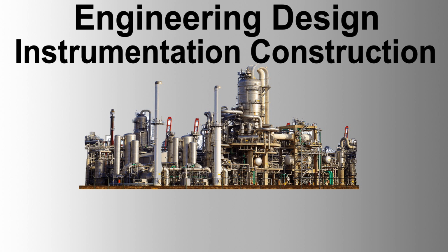Insulation shall be provided for impulse lines wherever required. The insulation should normally consist of mineral wool, wrapped around and covered with a weatherproof material. The chloride content in the mineral wool insulation shall not exceed 10 milligrams per kilogram. Technical requirements. Flow instruments. Differential pressure instruments for flow measurement should be located within a distance of 1 meter from the measuring element. Where this is not possible, e.g., due to limited accessibility of the connections, the instrument may be located away from the element, provided that the longer impulse lines will not cause measurement errors due to false static heads.